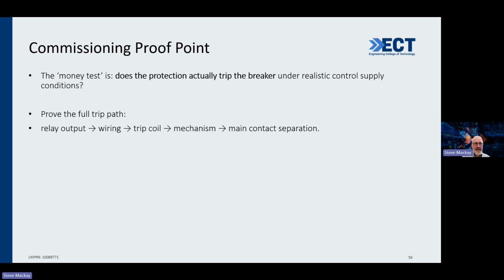So I suppose obviously the question is, does the protection actually trip the breaker under realistic control supply conditions? And obviously the other trick is to prove the full trip path from your relay output, the wiring, the trip coil, the mechanism, and the main contact separation.